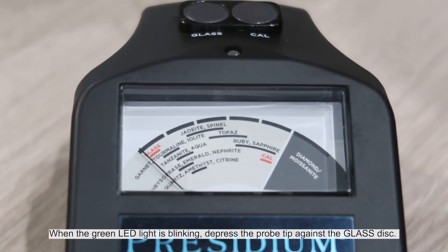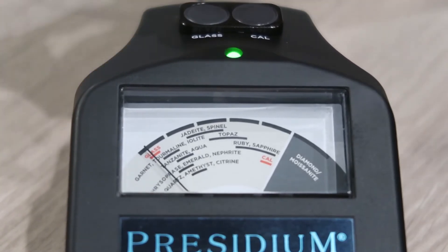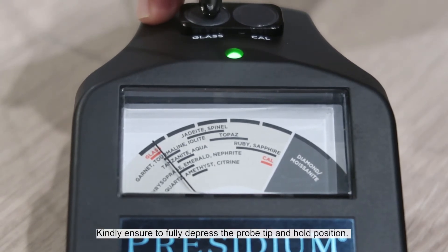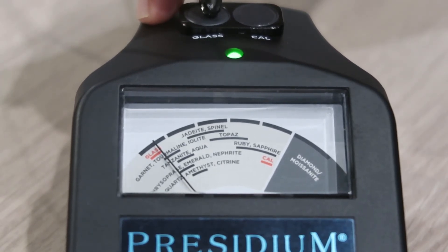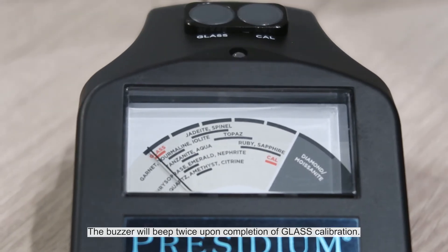When the green LED light is blinking, depress the probe tip against the glass disc. Ensure to fully depress the probe tip and hold position. The buzzer will sound twice upon completion of GLASS calibration.